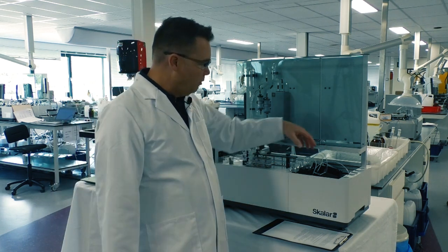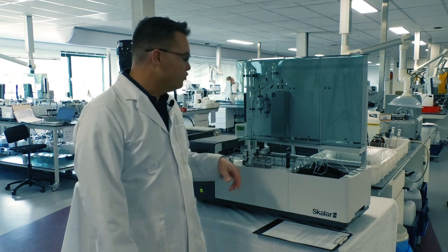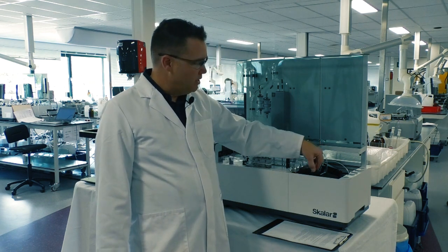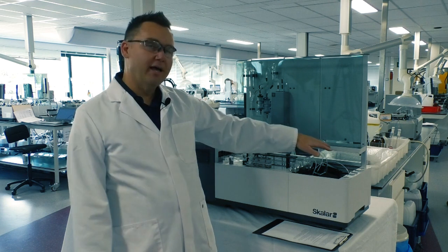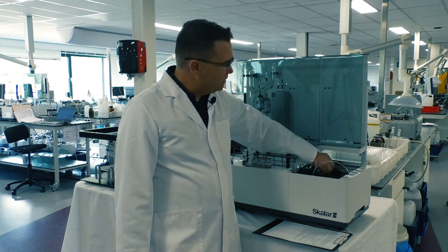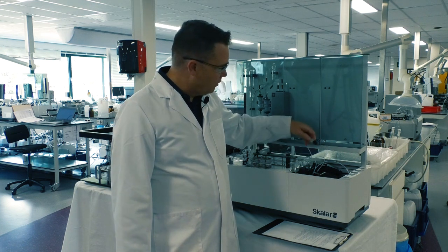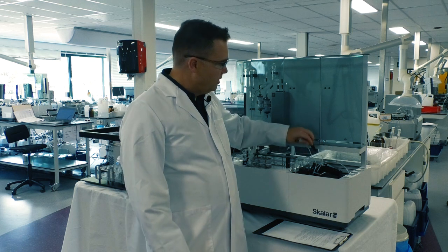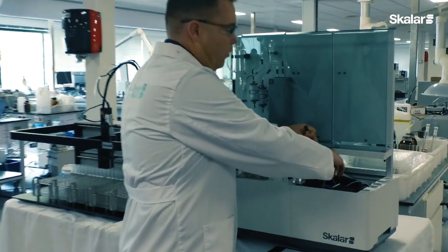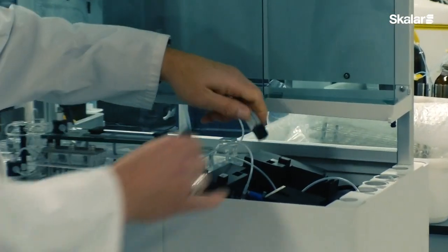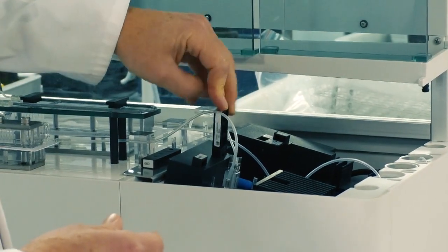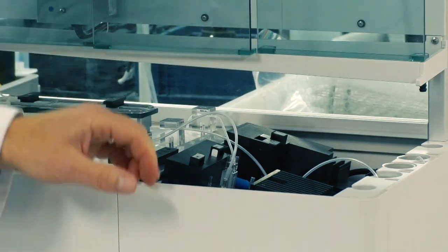So as you notice here, we've got a flow cell, and in this case, we're doing nitrate plus nitrite, which we're measuring at 540, and we have our 50 millimeter flow cell here. So if I needed to, let's say I didn't have the second flow cell back here, and I wanted to run my cyanides, I can very easily take the cyanide flow cell along with its wavelength filter, and I can remove the one I have here for ammonia. I can easily move the ammonia wavelength filter, also its flow cell, and just place the flow cell inside of the slot right there, and my wavelength filter, and voila, I'm ready to go.